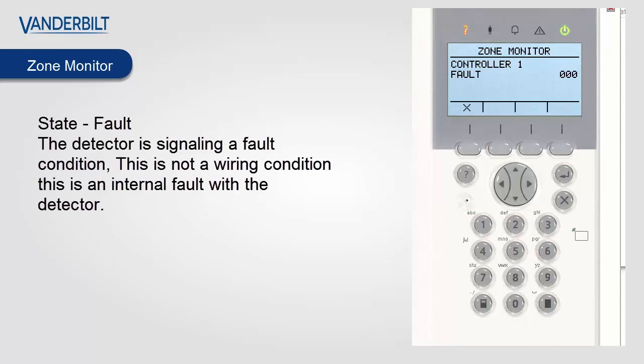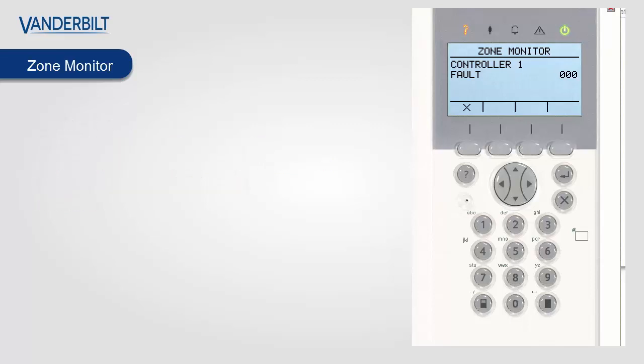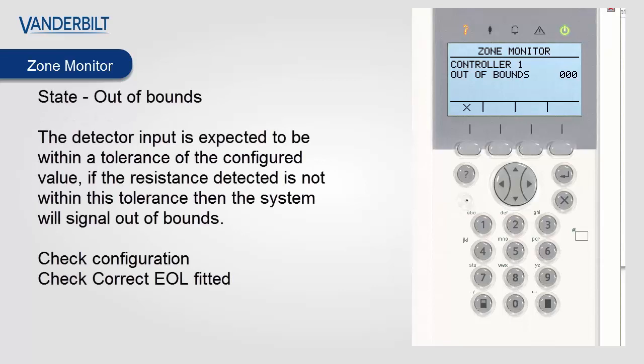Zone state fault: certain detectors will run internal tests and can signal a fault condition. This is not a wiring condition — this is an internal fault with the detector. Zone state out of bounds: the detector input is expected to be within a certain tolerance of the configured end-of-line value. If the resistance detected is not within this tolerance the system will signal out of bounds. Please check the end-of-line configured, and if you perceive this value to be correct you may switch the system to use wide range end-of-line.